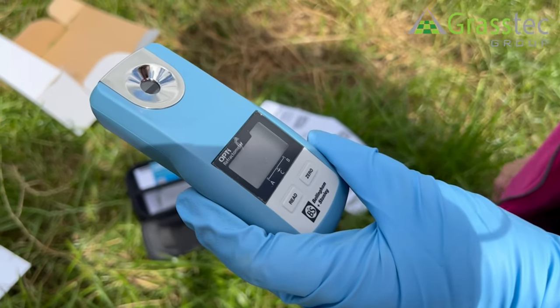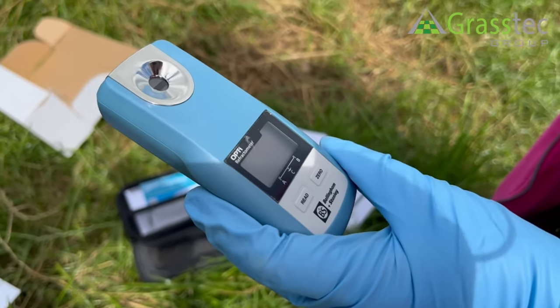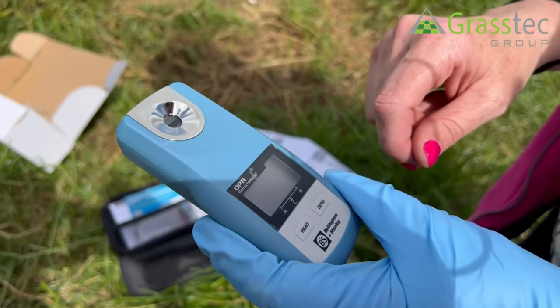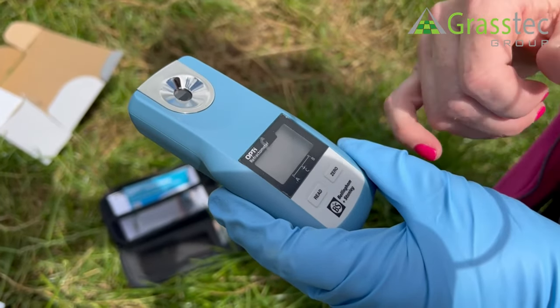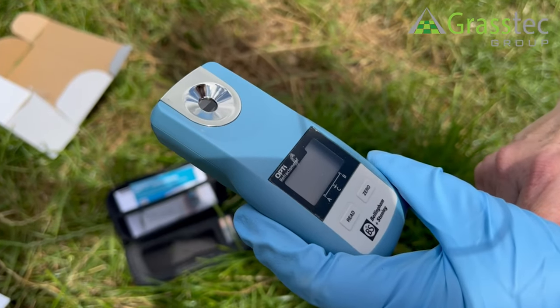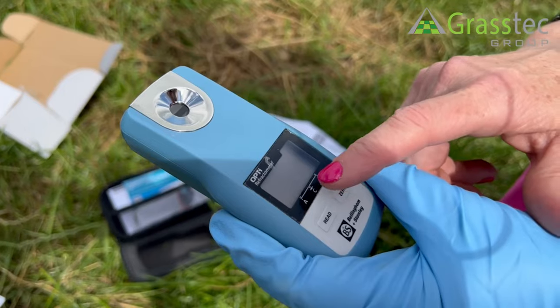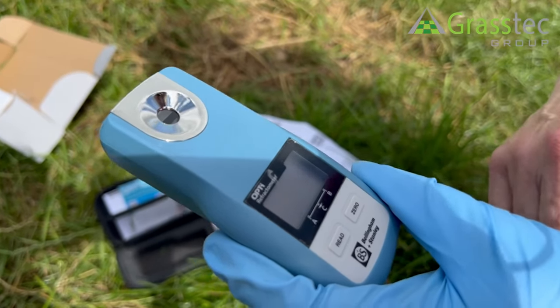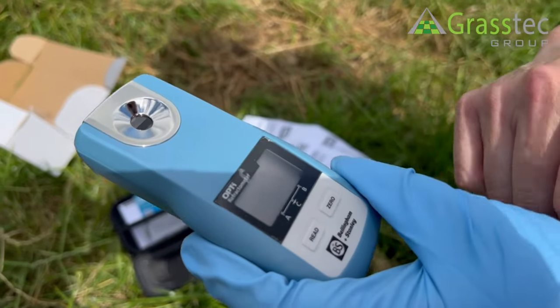Here we have an OPTI digital refractometer. It's easy to use — you just put your sample in here and press the read button. It's set for three modes: A is brix in grass sugars, B is colostrum sugars, and C is antifreeze.